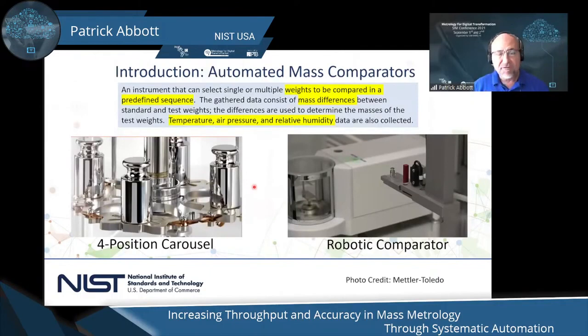So just to give you a better feel for what these automated mass comparators look like, first, let's talk about what we mean by an automated mass comparator. I've made a little definition here. An automated mass comparator is an instrument that can select single or multiple weights to be compared in a predefined sequence. The gathered data consists of mass differences between standard and test weights, and then these differences are used to determine the masses of all the weights tested. And of course, environmental variables like temperature, air pressure, and relative humidity are also collected.